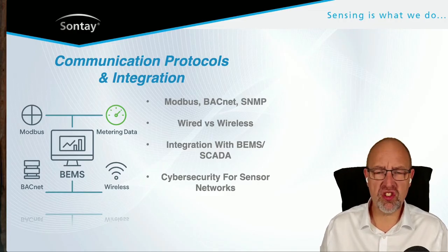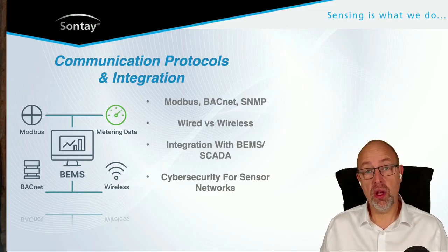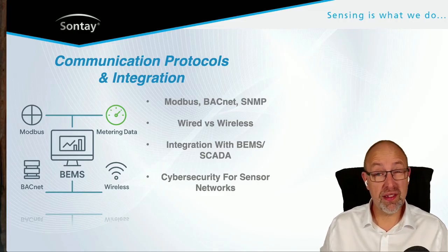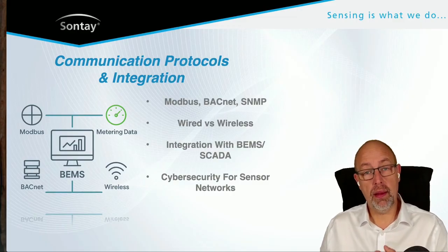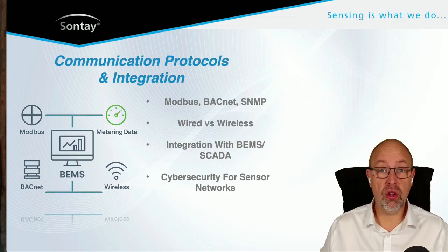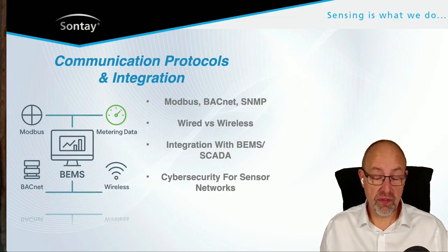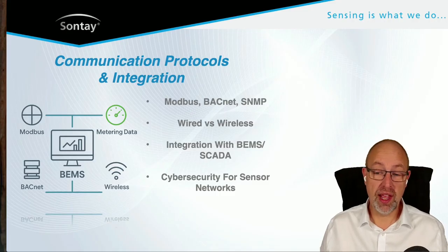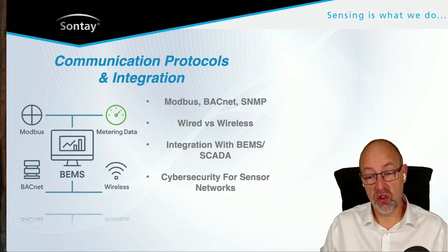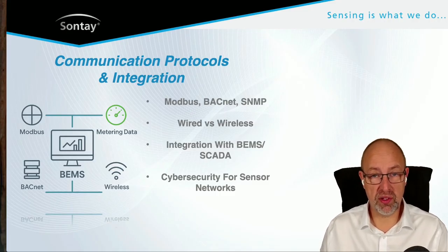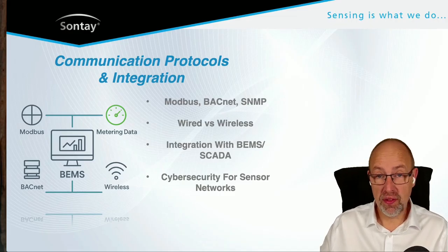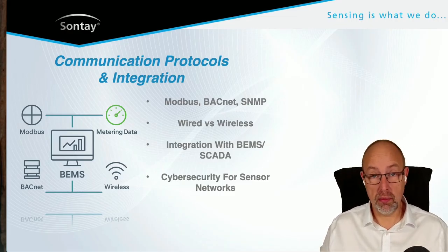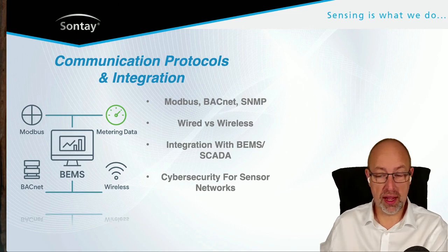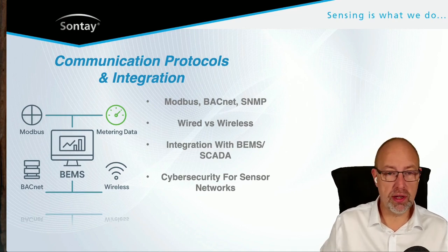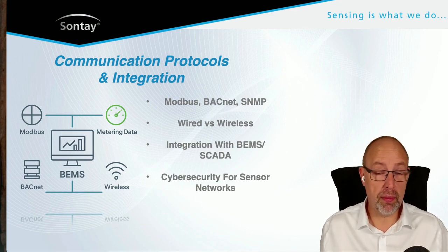But we also get smart sensors, and smart sensors are great because they sit on a digital bus, and because they sit on a digital bus, they are lossless. You get the information passed down a digital bus, and it's in ones and zeros, so you get accurate information passed down the digital bus. If that information isn't received, so you get an error code, a CRC, cyclic redundancy check, which is not right, then you can request the data again. So they're really good from that point of view.